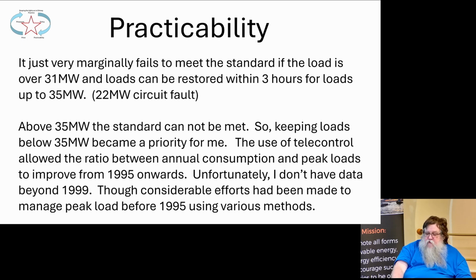So when I was managing the demand in Orkney by switching teleswitch times, the total control and the white meter and all the other ones that were available were switched at various times to keep the load below 35 megawatts. That was my priority. I used to be in the power station Monday to Friday every morning. What happened last night? Did what change? Did the previous day's change make it worse or make it better? And then to keep it below 35 megawatts.